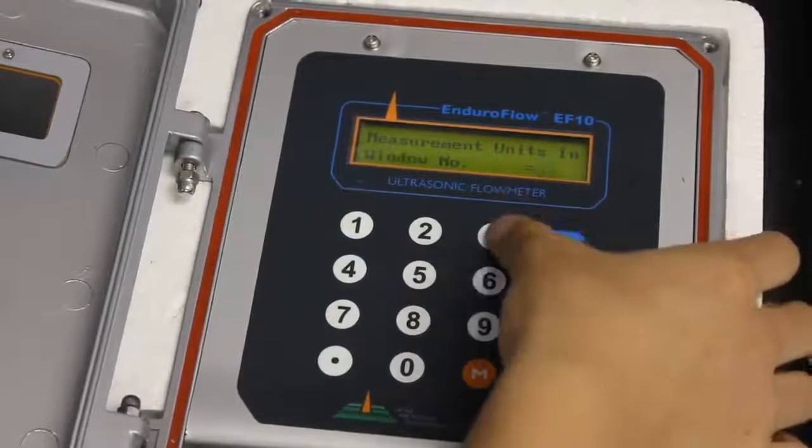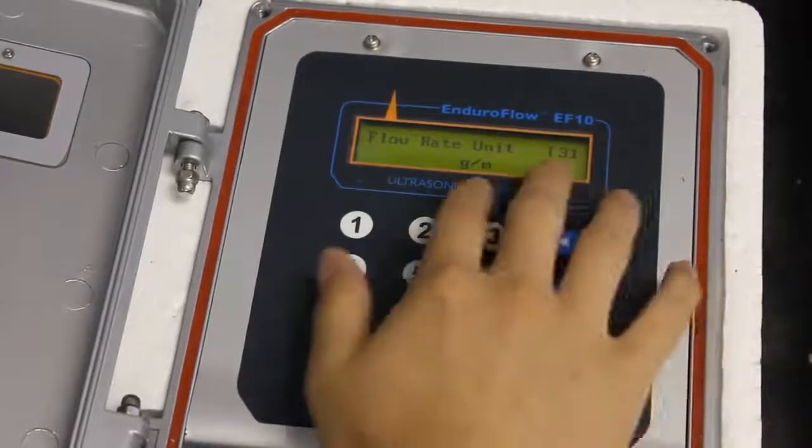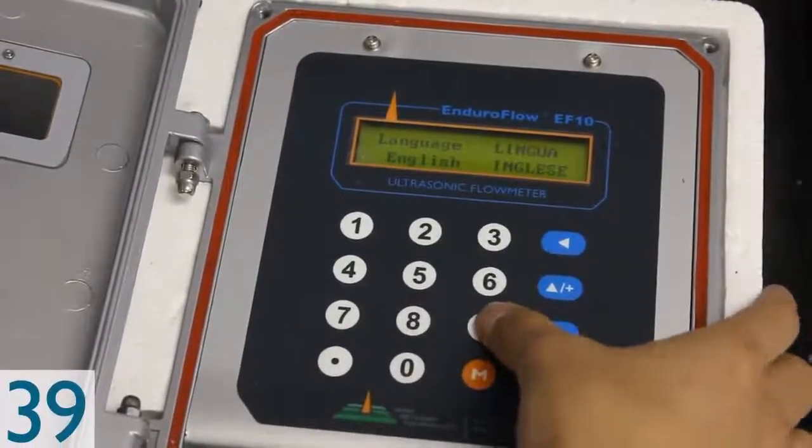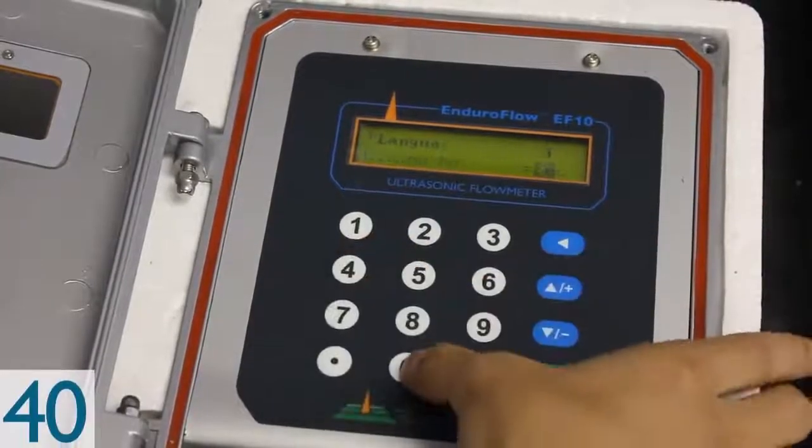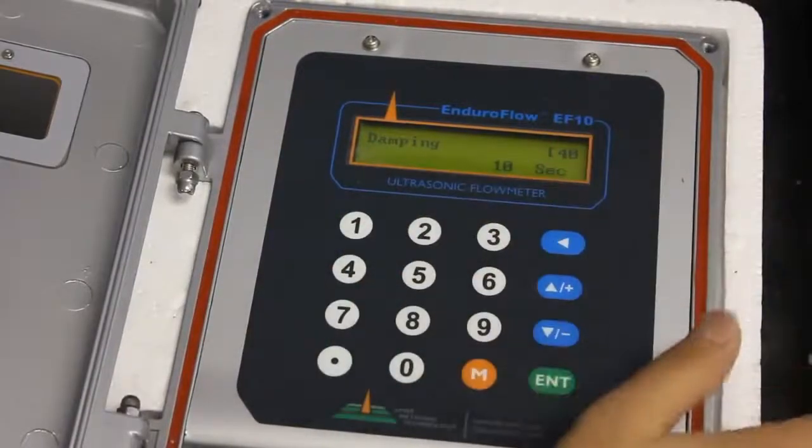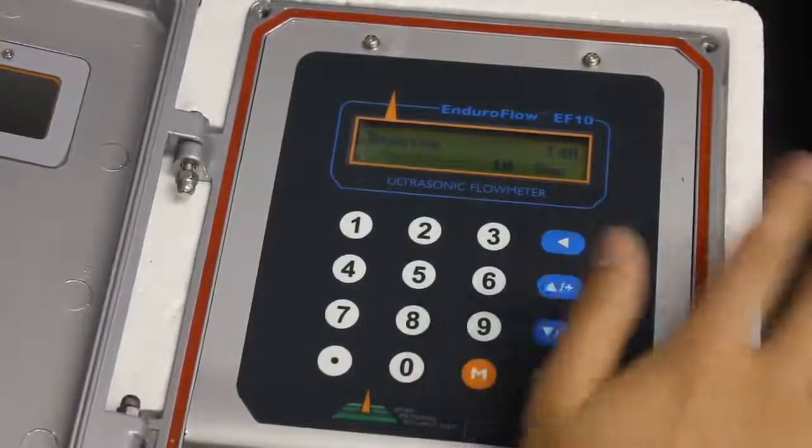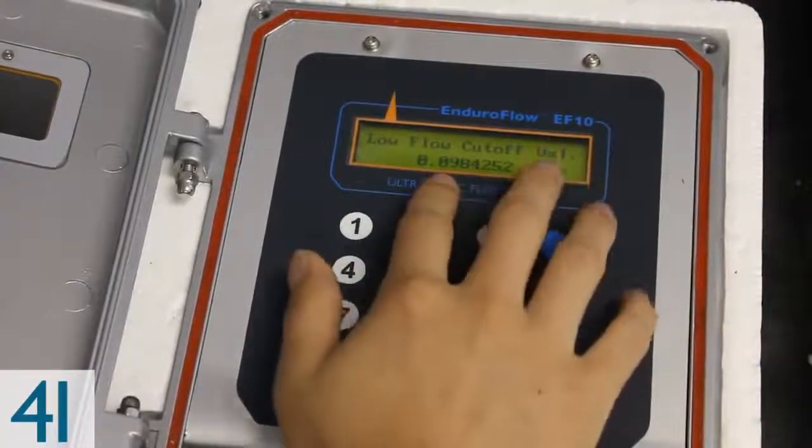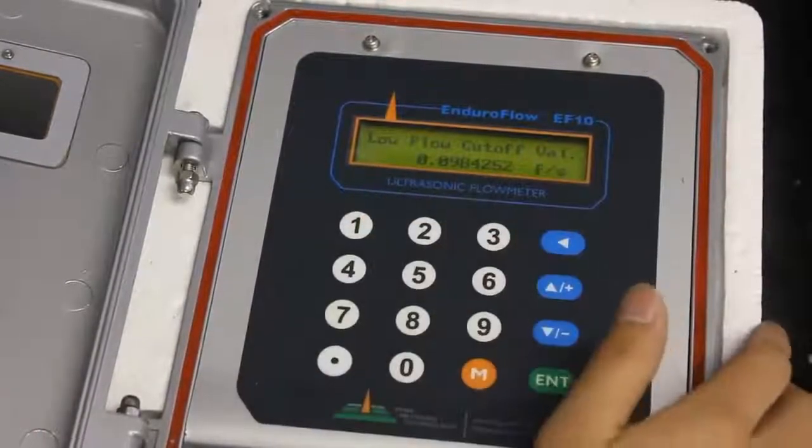Next we go to menu 31 to set the flow rate unit, which is already in gallons per minute here. Then we go to menu 39 to set the language, it's already in English. Next we go to menu 40 to set the damping. You can do 10 seconds or 20 seconds, both are fine. This basically takes average of the flow over this amount of time. Next we go to menu 41. This is a low flow cutoff value. We already calibrate them to the factory standard here so you don't need to worry about that.